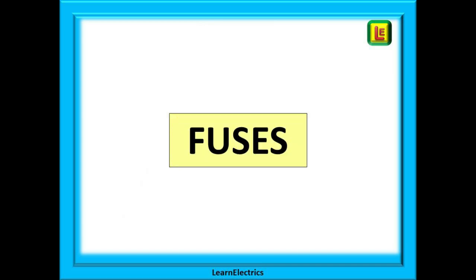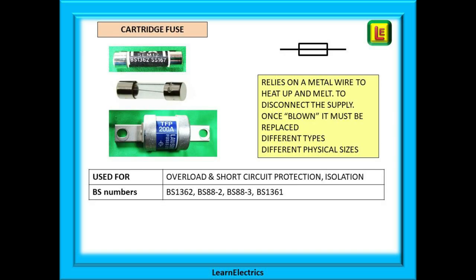Let's start with fuses. We begin with cartridge fuses — they are still very common and used throughout the electrical industry. The symbol most of us use is shown at the top right: an oblong with a line through it to represent the fuse wire. They rely on a piece of metal, the fuse wire, to melt when excessive current flows through the fuse. When the wire melts or blows, this creates a gap and interrupts the flow of current. Once blown, the fuse must be replaced — they are a simple one-shot device.